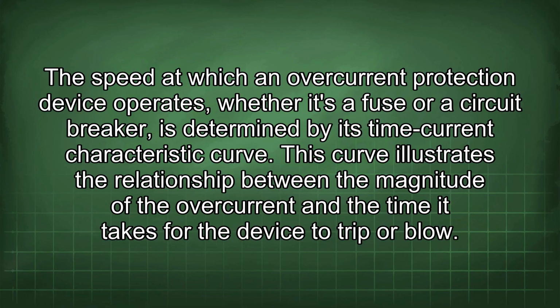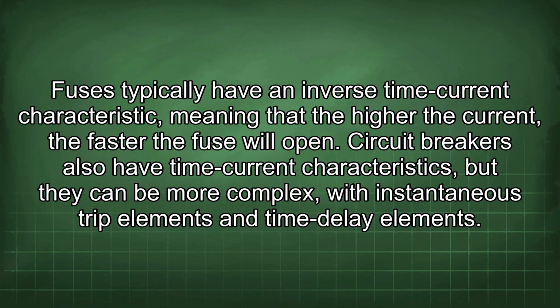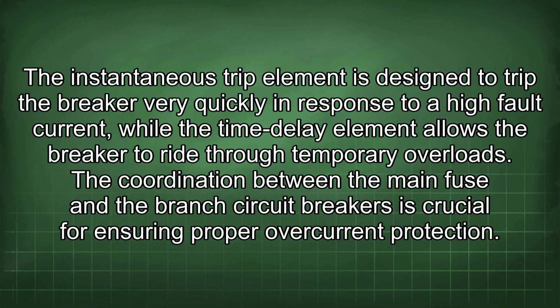trip or blow. Fuses typically have an inverse time current characteristic, meaning that the higher the current, the faster the fuse will open. Circuit breakers also have time current characteristics, but they can be more complex with instantaneous trip elements and time delay elements. The instantaneous trip element is designed to trip the breaker very quickly in response to a high fault current, while the time delay element allows the breaker to ride through temporary overloads.